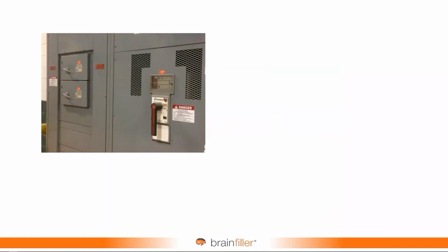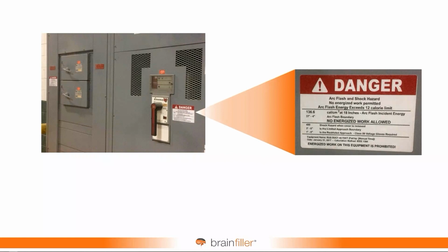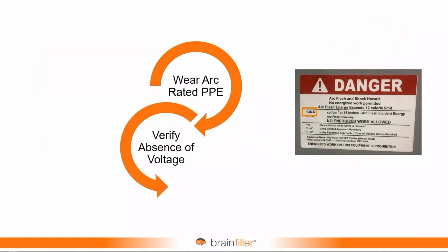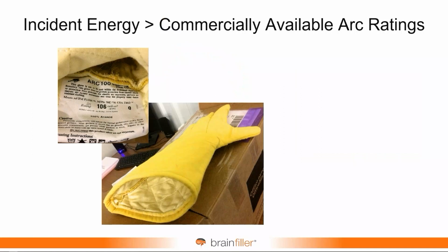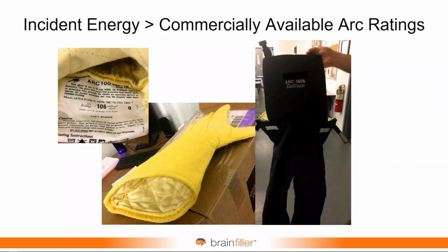There is this ongoing issue of establishing an electrically safe work condition, especially when you have extremely high incident energy values. And the issue is, an extremely high incident energy value, okay, we better establish an electrically safe work condition. But we need PPE to do that because we assume that it is energized until we've established absence of voltage. There is arc-rated PPE out there with very high arc ratings. This one is 140 calories a square centimeter on the right, but most don't have this.